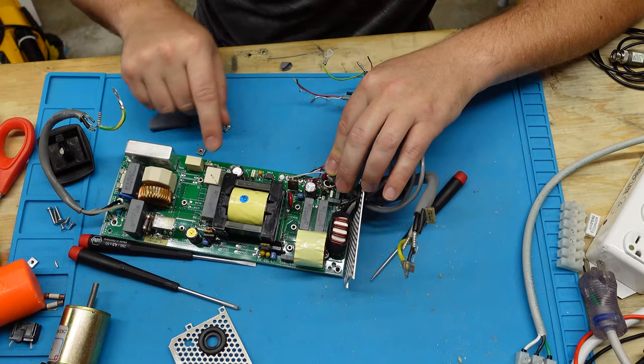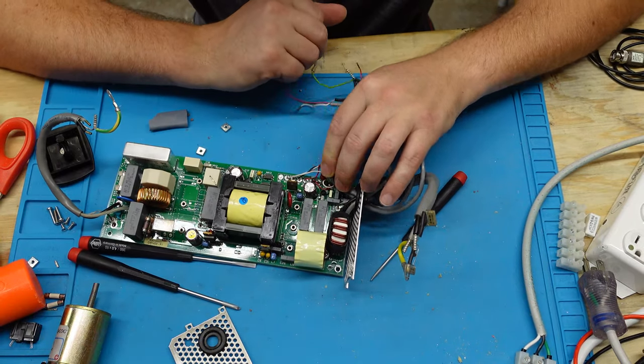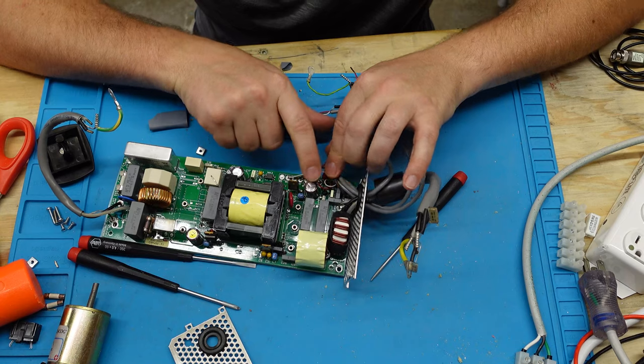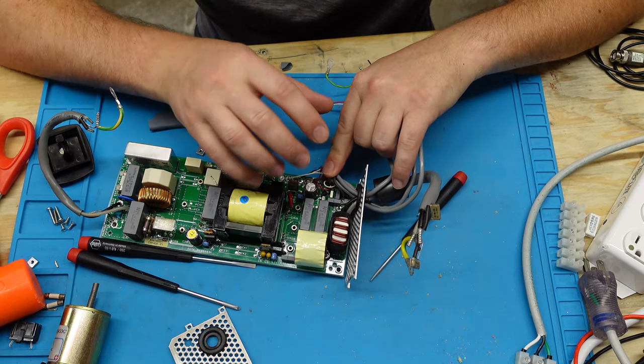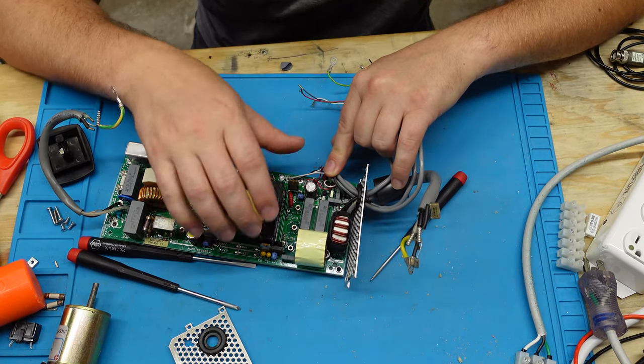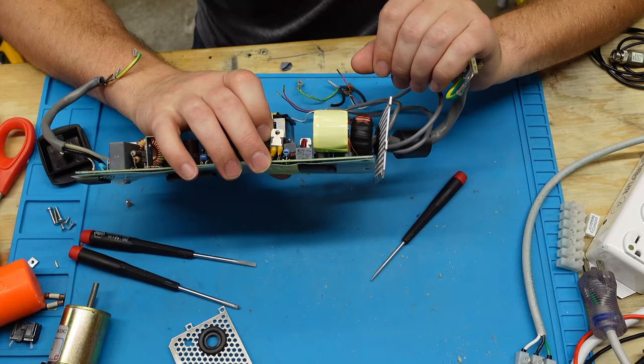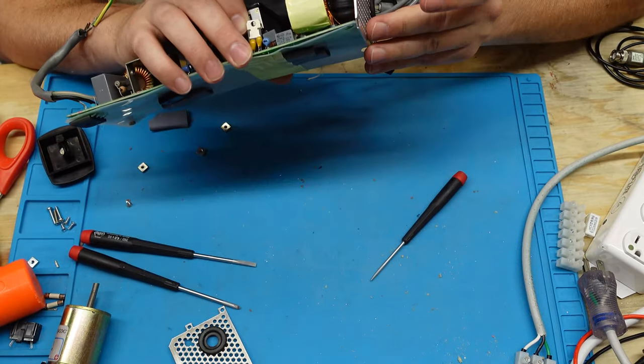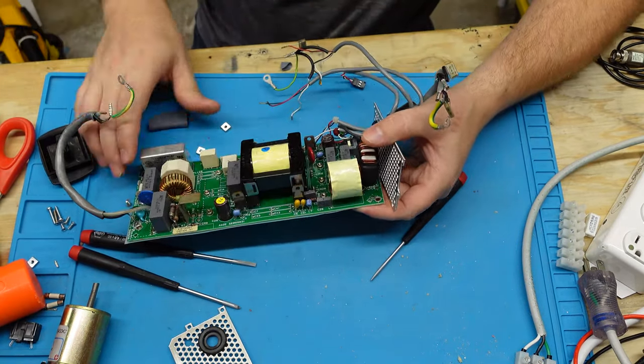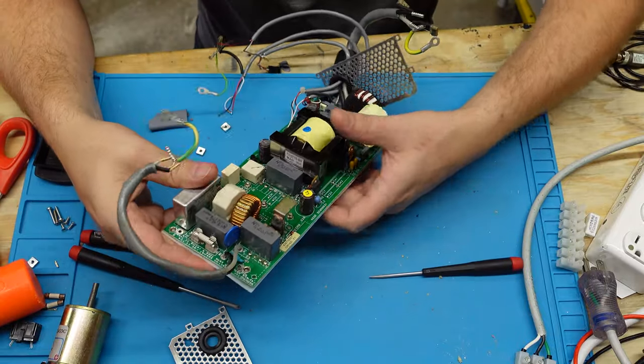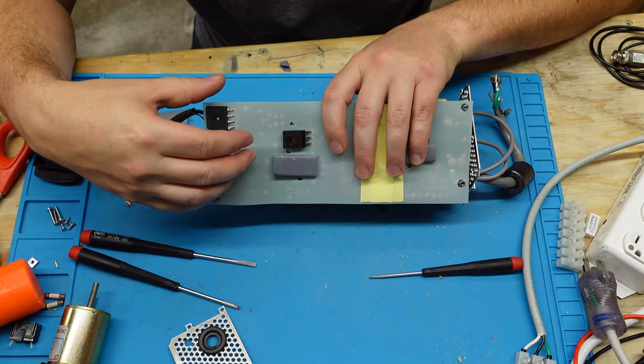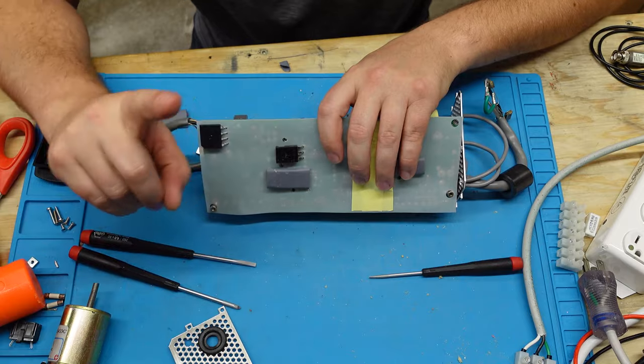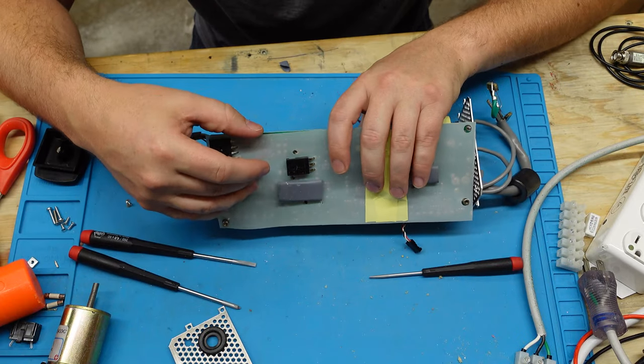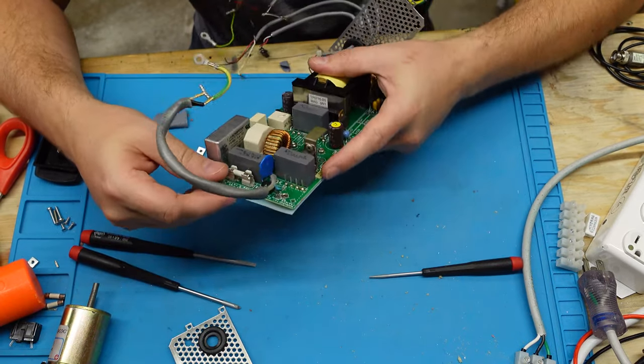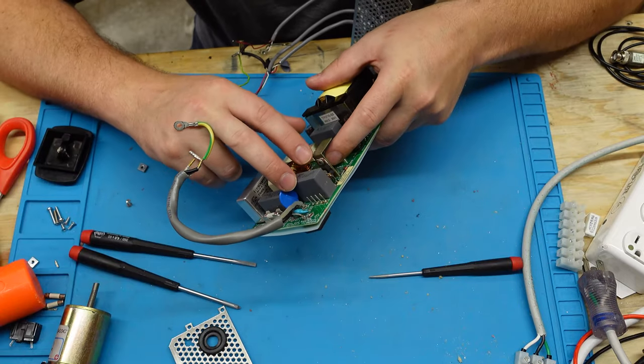The capacitors look like they're solid. Often, especially over here on the output side, you'll see these capacitors get very bubbly, they'll leak. It's looking pretty good. Transformers all smell fantastic, like regular electrical components. I know you guys probably think it's weird that you smell a board, but believe it or not, smelling a board will really help you find other problems.